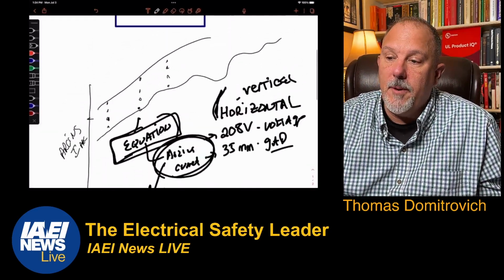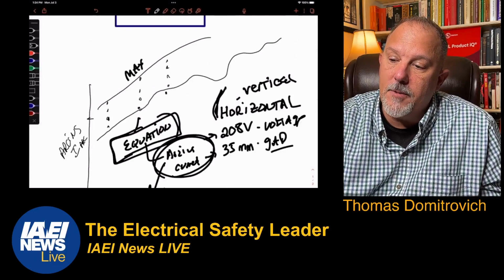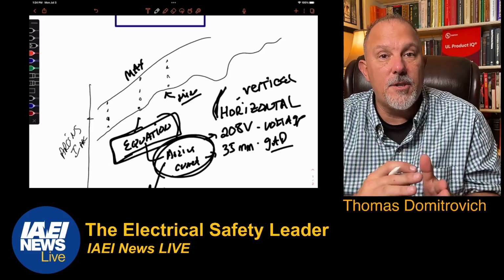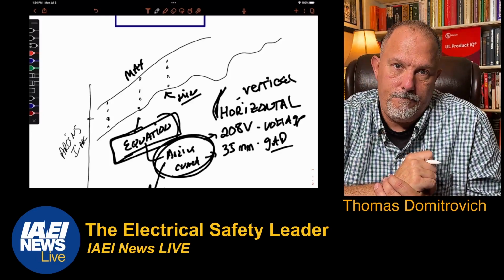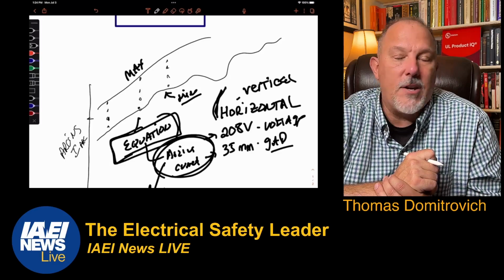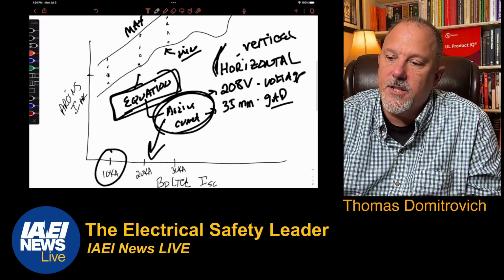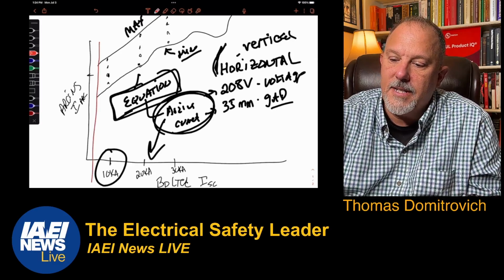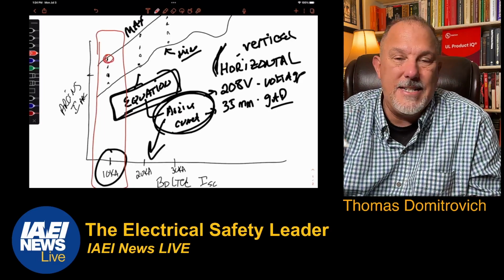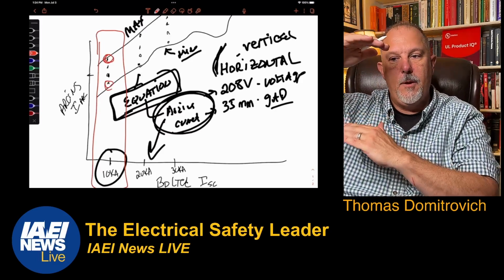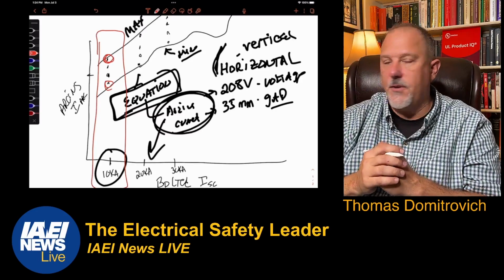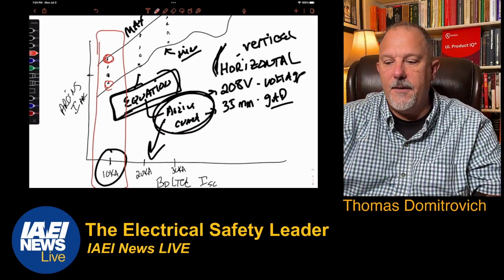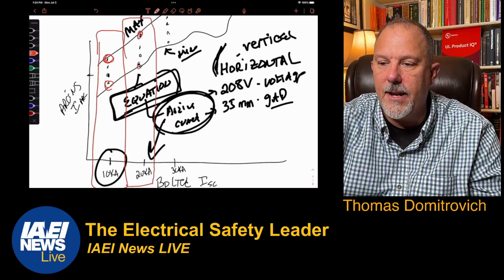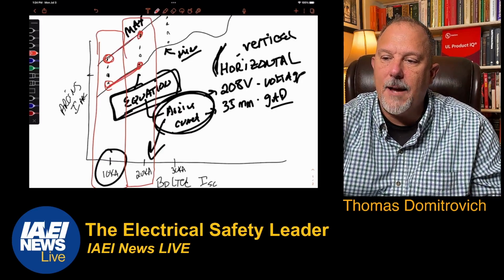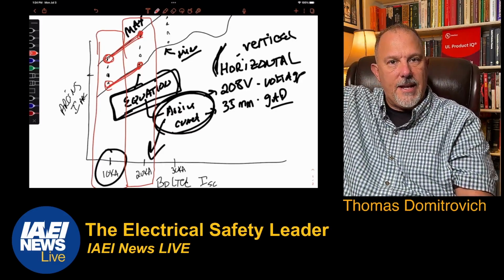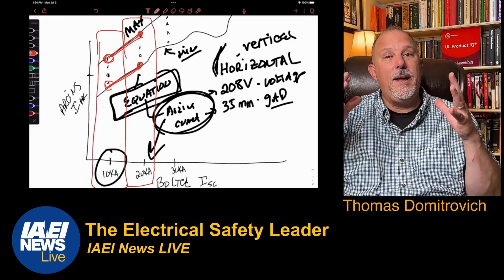And when we say minimum, what do we mean by minimum? So this is your maximum, and this bottom curve is your minimum. And where do those numbers come from? Those numbers come from the variations in impedances, because no two arcs are the same. So for this 10 kA available fault current, my maximum data point and my minimum data point establishes the, what do you call that? The zone, right? You have a maximum number and you have a minimum number. And every available fault current after that, I have a maximum and I have a minimum. And then I have to just be able to establish an equation that will follow the maximum data points that I have and the minimum data points that I have. So you have two basic equations.